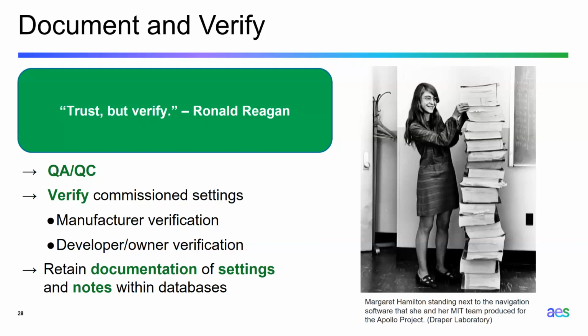On the manufacturer side as well, how do you set up your company to make sure these are quality checks? Because they're very important. Your inverter can drop off, or you can limit yourself with your megawatts, MVA, or MVAR — limiting it so you're not even able to output as much as you really could from that inverter. The power plant controller often limits it anyway, but we won't get into that.